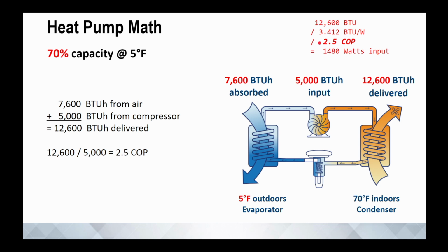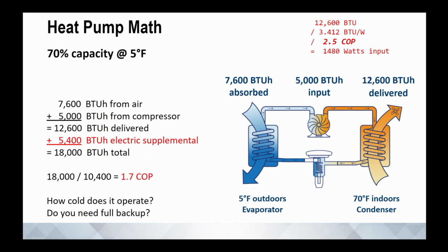Yes, it's more efficient, but we're not getting enough, because what they're doing is they're dialing back how much energy goes into the compressor. They're pulling back and saying, I'm not going to invest as much. Yes, I'm getting a pretty good absorption rate. I'm getting pretty good efficiency. I just am not investing as much, so I'm not getting as much out of it overall. So what do we have to do? We have to add in additional heat. We have to make up for that 30%, right? So maybe that's electric supplemental heat, like a strip heater, whatever you want to add in, the space heater, etc.